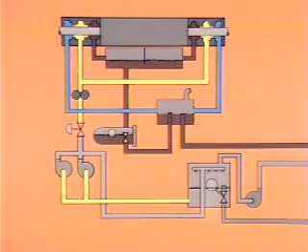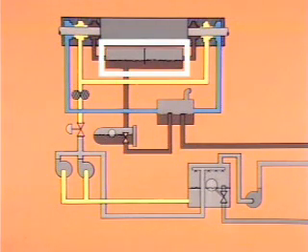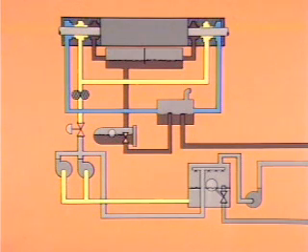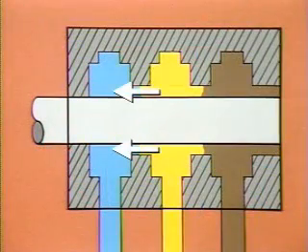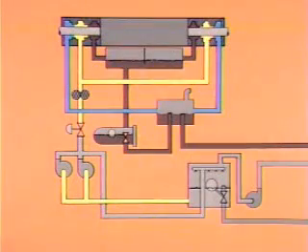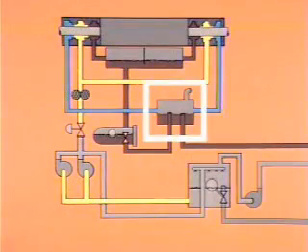Any hydrogen that is absorbed by the oil is carried to a container called a detraining tank. If the pressure in the seal oil system drops for any reason, hydrogen might be released into the atmosphere or into the air side of the oil seal. To prevent a drop in oil pressure, the seal oil system is equipped with a backup circulating pump that may be battery-powered. The rest of the oil flows toward the air side and carries the air into another detraining tank.